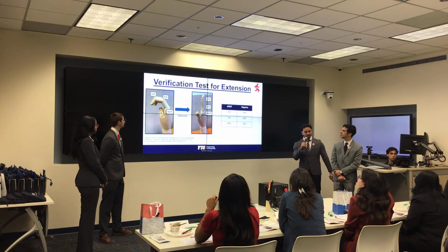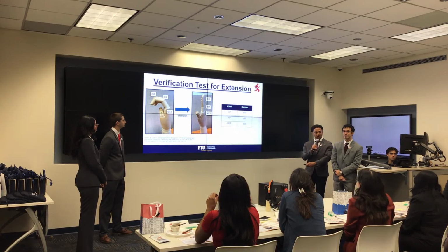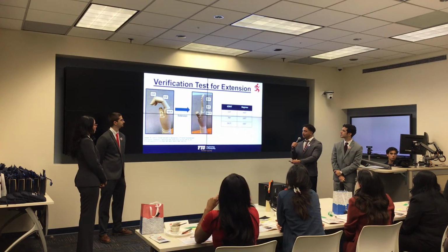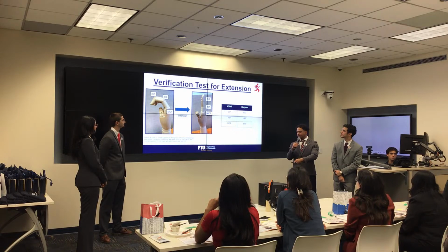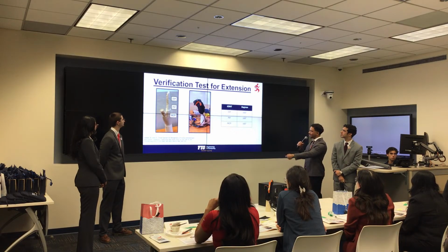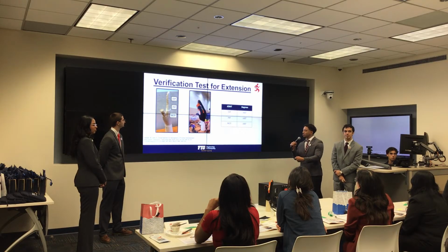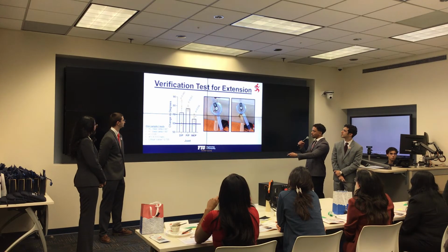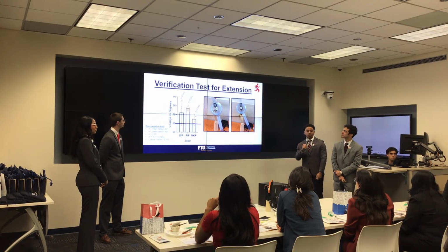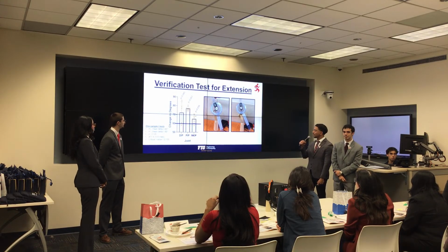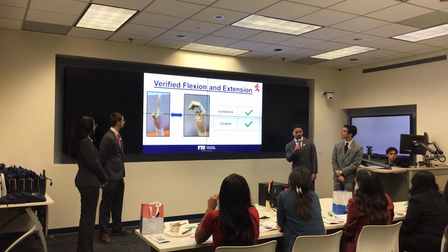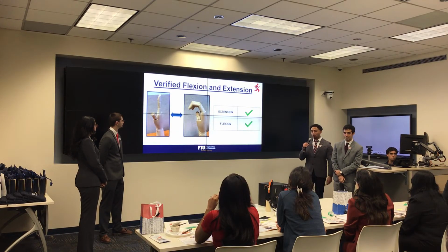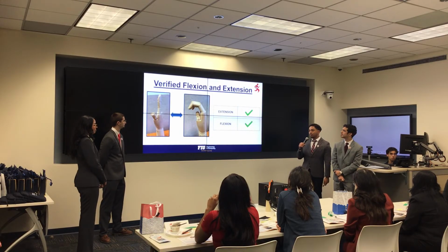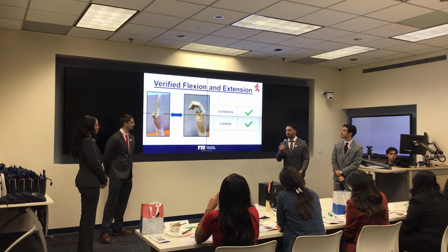So we then began extension, same criteria, a minimum of 60 degrees for acceptance. And we did a naturally curled and then using the extension. So this is a video of how it looks like. And as you can see, it extends up. So we did that several times, and we got this graph here to show that it's statistically significant, well above 60 degrees for all the joints. And as we can see for the verification, it passed both tests. So we now know that the mechanical aspect is sound, but we need to incorporate with the EMG to see if it causes the rehabilitation.